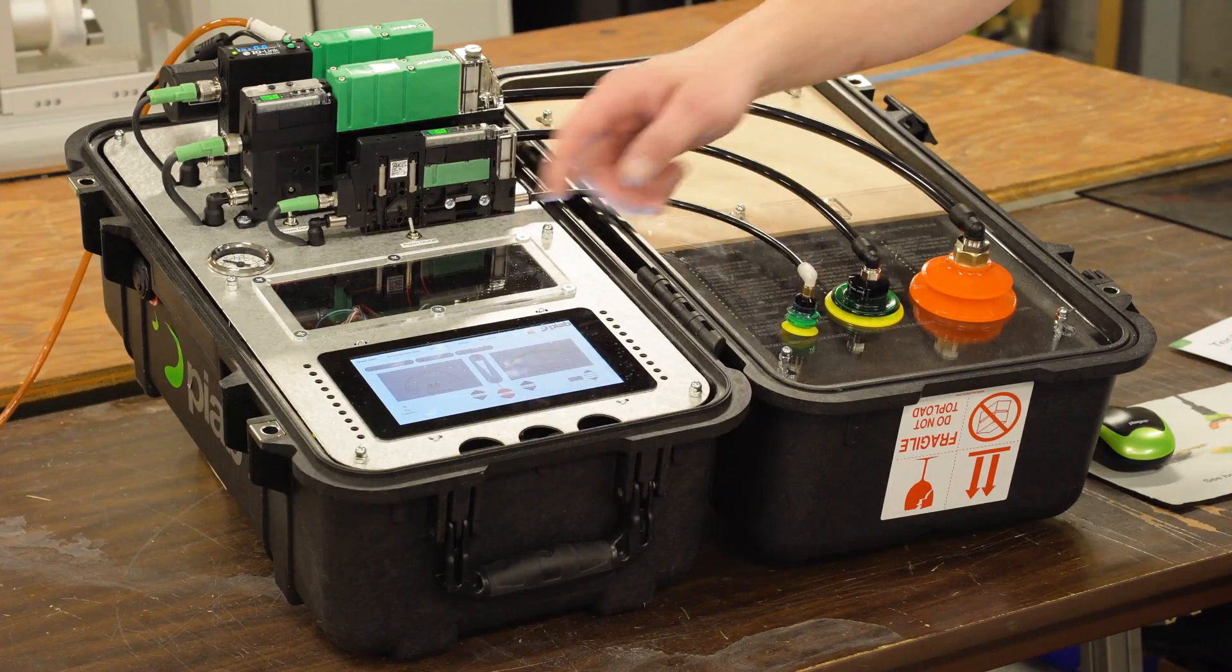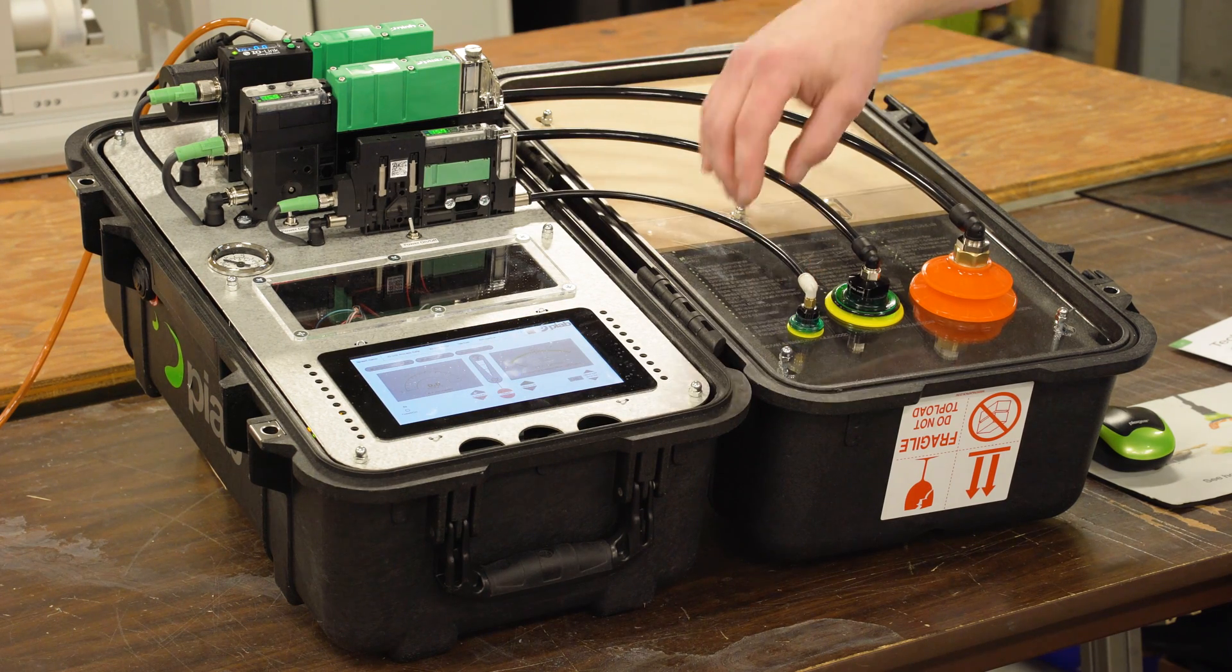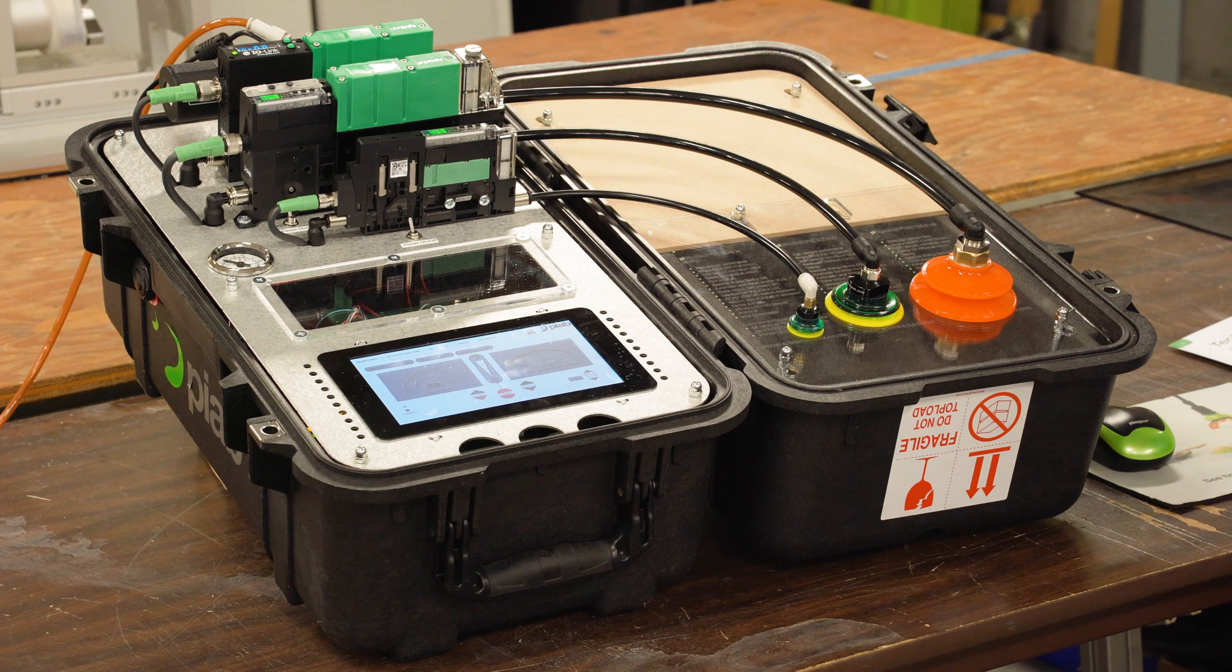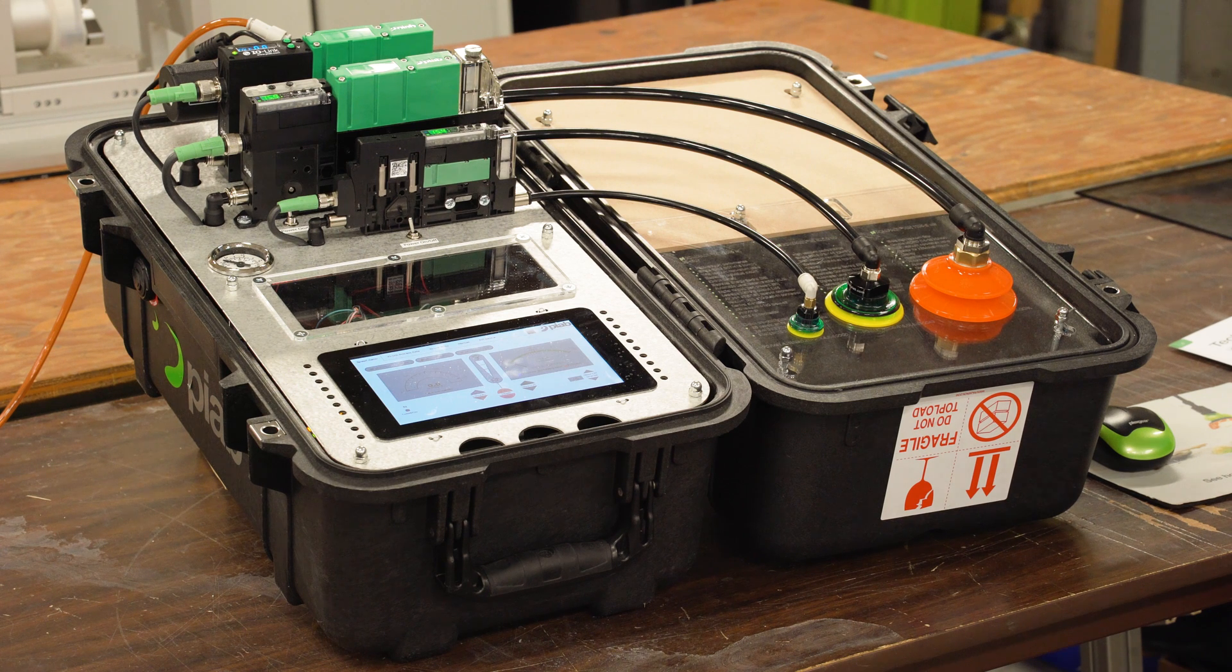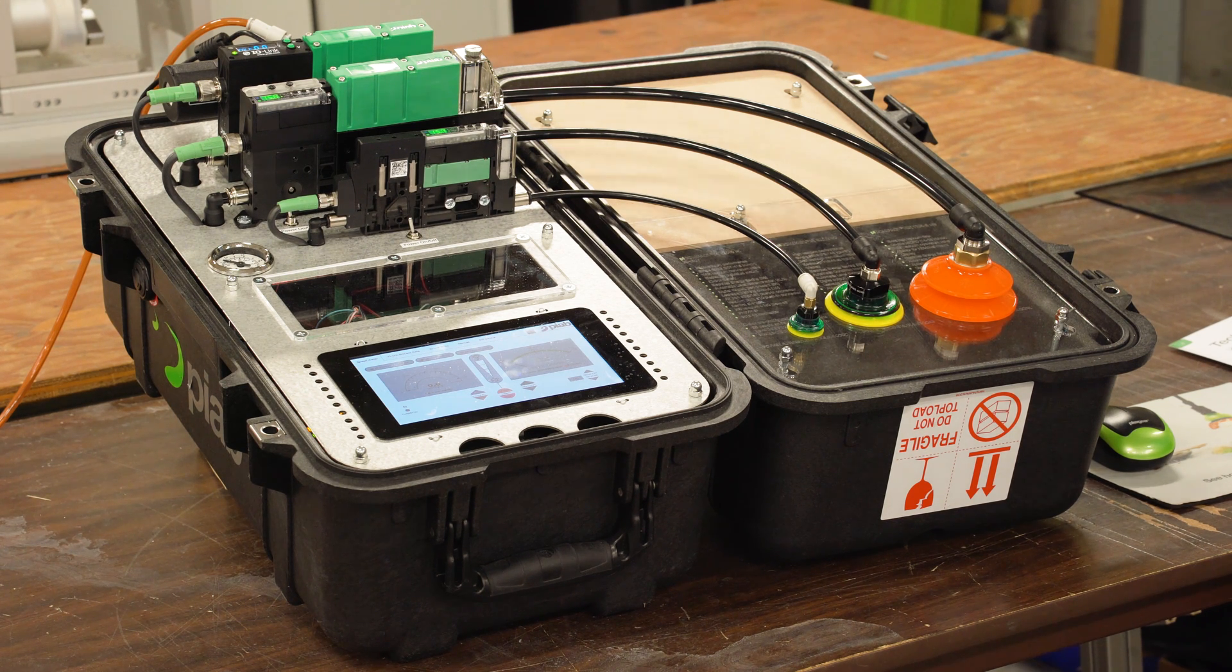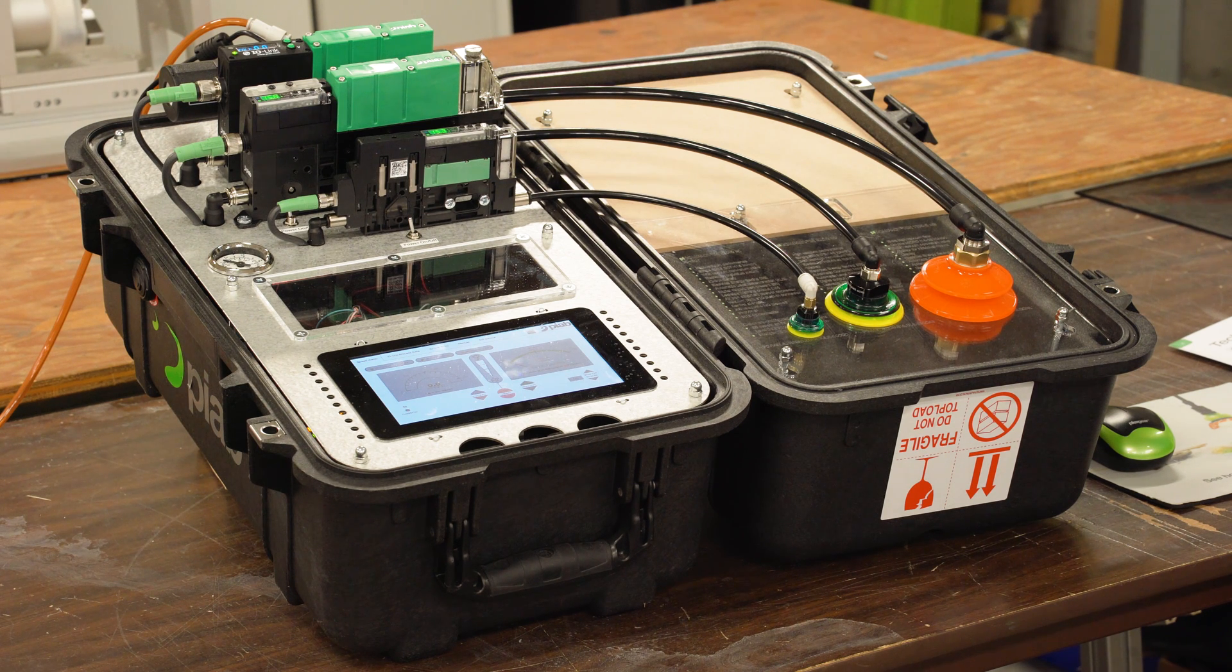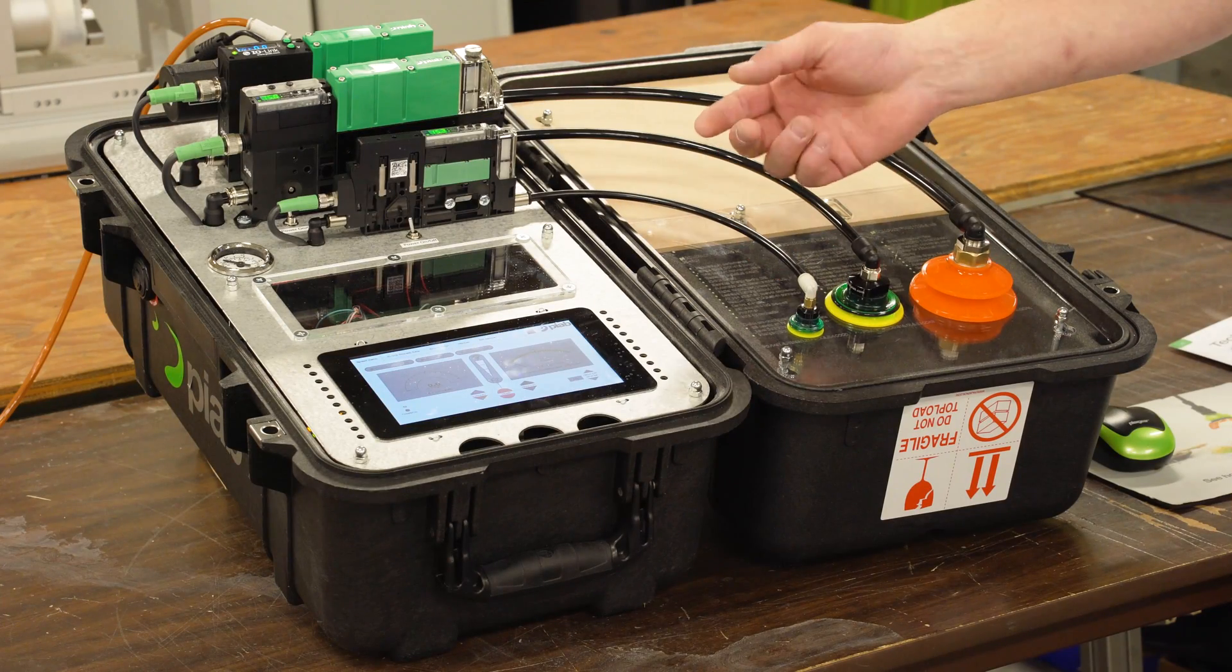So when I have a no-leak application, my compressed air shuts off. I'm no longer using compressed air, so the longer you're holding something, the more you're going to take benefit of this. But a side effect to it is the silence of it. If you have an operator standing next to that ejector all day long, it's that much less compressed air purging into their ear. So a little bit more enjoyable to work around.